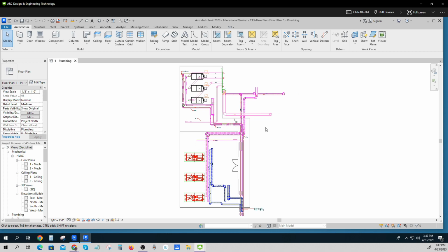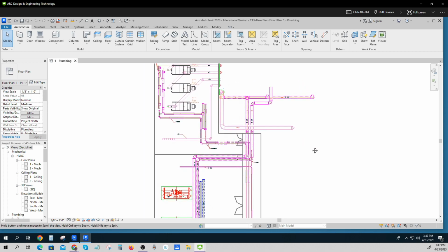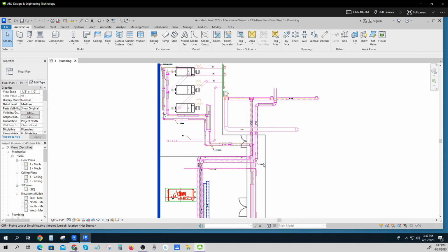And some of you might have heard me talk about the job where the boilers didn't fit. There's all this work that shows that they can be rolled from this area through these doors and into here, and everything fit except the fact that these doors were too low because of the 3-inch diameter rollers that these had to be put on. Then they didn't fit.